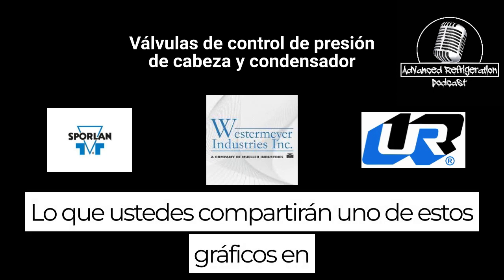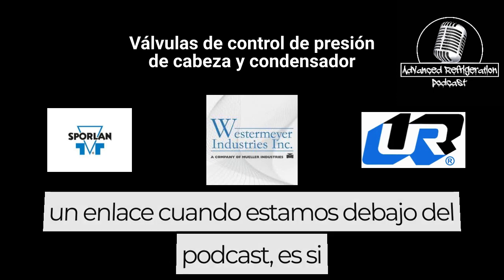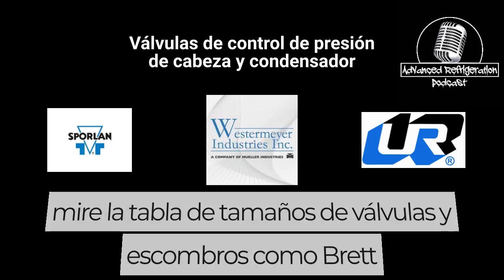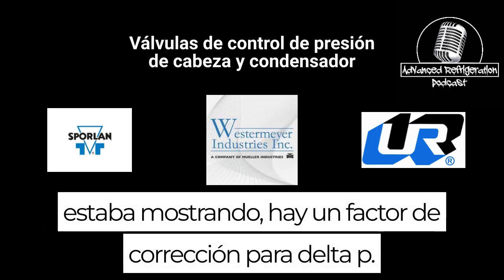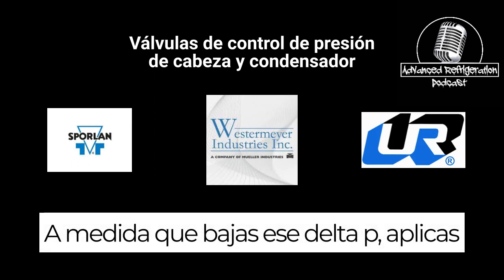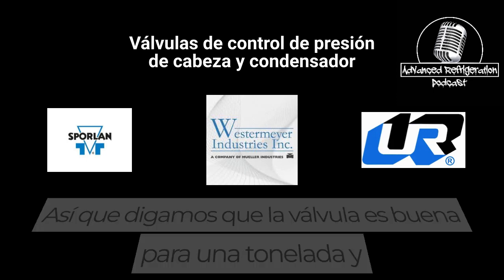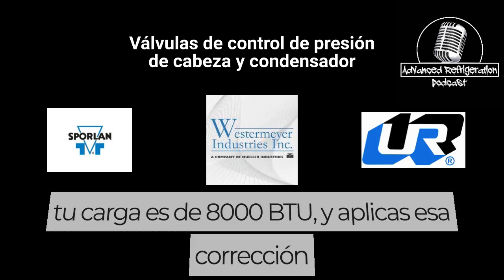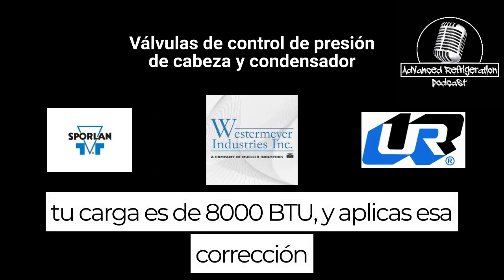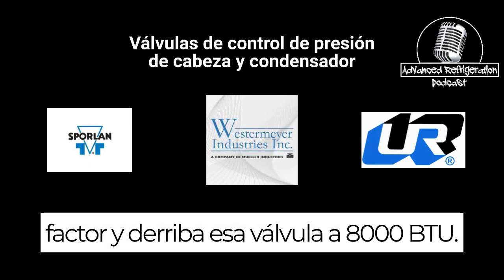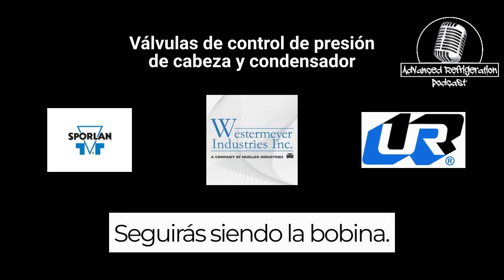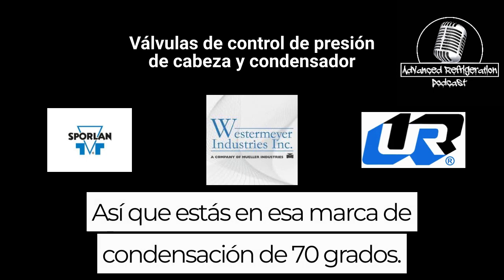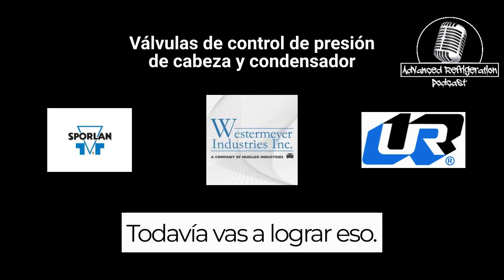We'll share one of these charts in a link with the podcast. If you look at the valve sizing chart like Brett was showing, there's a correction factor for delta P. As you lower that delta P, you apply the correction factor to the valve sizing. So say that valve's good for 1 ton and your load's 8,000 BTUs, and you apply that correction factor and it knocks that valve down to 8,000 BTUs. Okay, you're still good. You're still going to feed the coil. So at that 70 degree condensing mark, you're still going to accomplish that.